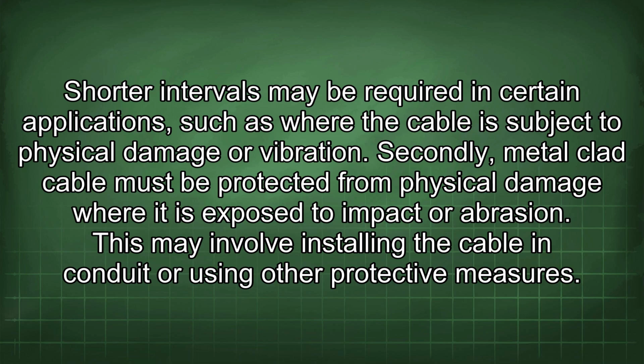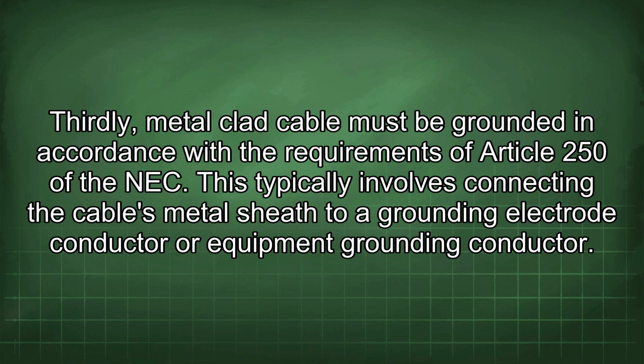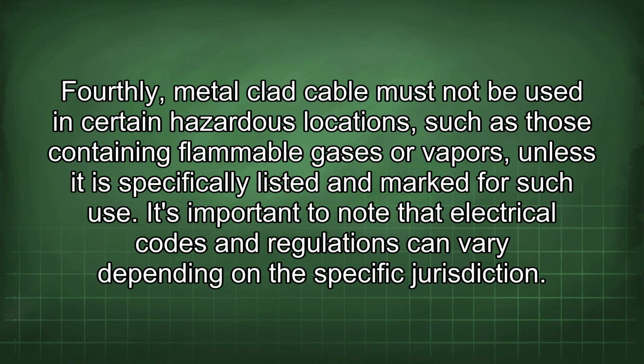Secondly, metal-clad cable must be protected from physical damage where it is exposed to impact or abrasion. This may involve installing the cable in conduit or using other protective measures. Thirdly, metal-clad cable must be grounded in accordance with the requirements of Article 250 of the NEC. This typically involves connecting the cable's metal sheath to a grounding electrode conductor or equipment grounding conductor. Fourthly, metal-clad cable must not be used in certain hazardous locations, such as those containing flammable gases or vapors, unless it is specifically listed and marked for such use.